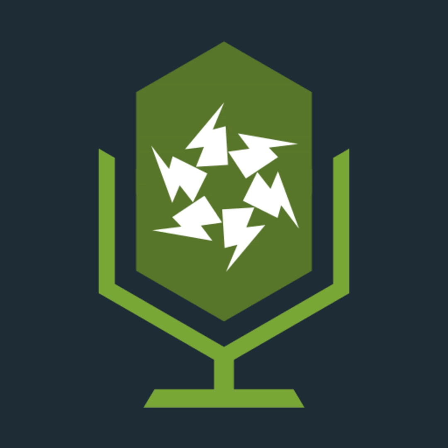So first thing it says is at point of entry to the premises, or the most accessible part after entry to the premises. Where there is a meter, isolation point, or union, the connection shall be made to the consumer's hard metal pipework and before any branch pipework. Where practicable, this shall be made within 600 mil of the meter outlet union or at any point of entry to the building if the meter is external. Couldn't be simpler. If the meter is external, you bond it at the point of entry to the building. Don't take your bond outside.